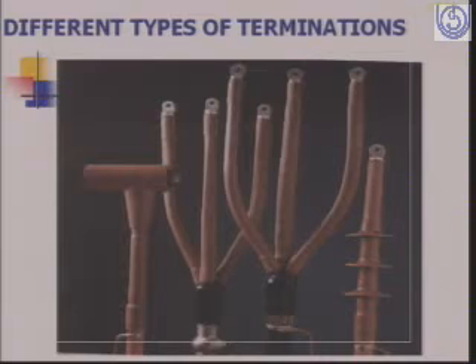Then we have the aerial bunched cables. Aerial bunched cable is a cross between the overhead and the underground cable. So the aerial bunched cable is a cable which can be used above the ground, and it is used in place of overhead lines to prevent theft by the consumers. You can hook overhead lines, because in overhead lines they are bare conductor. You can hook the bare conductors, but with aerial bunched cables, it will be difficult to remove the insulation.